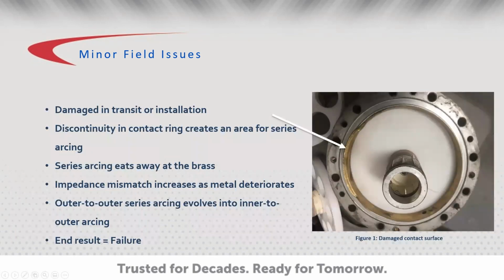Okay, so right here shows what I just mentioned, the folded contact surface on the gas barrier. This most likely occurred during transit or installation, as it would never leave the factory this way. This discontinuity creates an area susceptible to series arcing from the outer conductor to the outer conductor. And then over prolonged occurrence, the impedance mismatch at this location increases, arcing becomes more frequent, and the metal will continue to deteriorate.